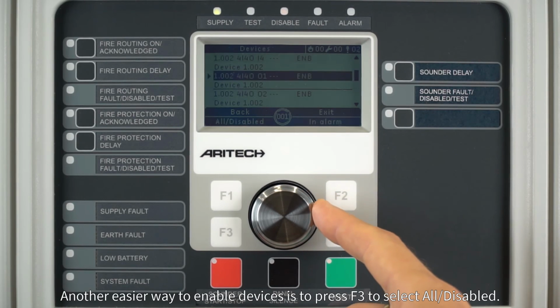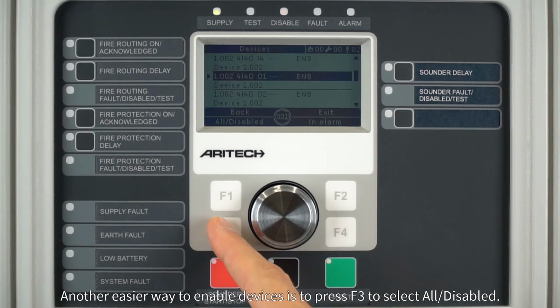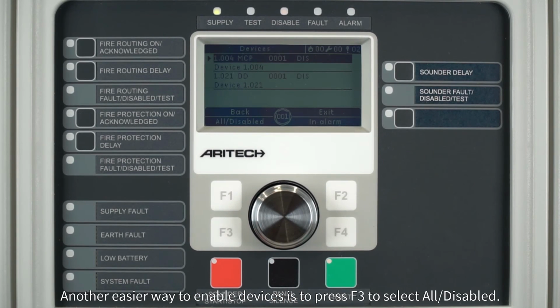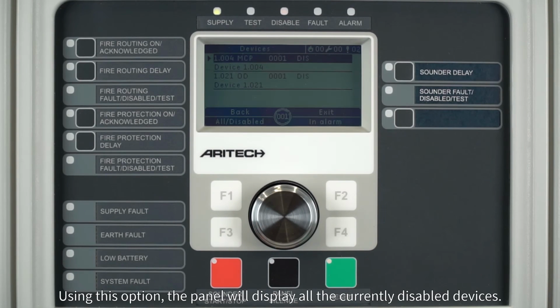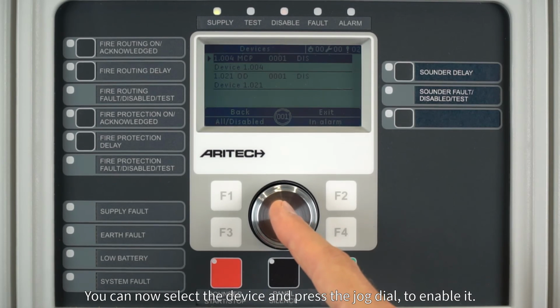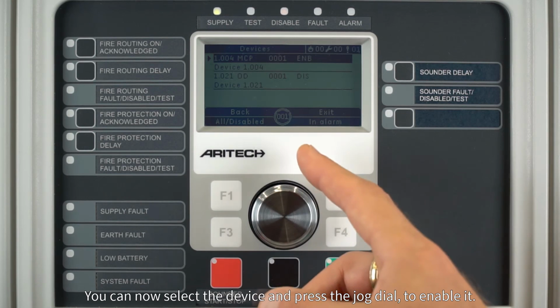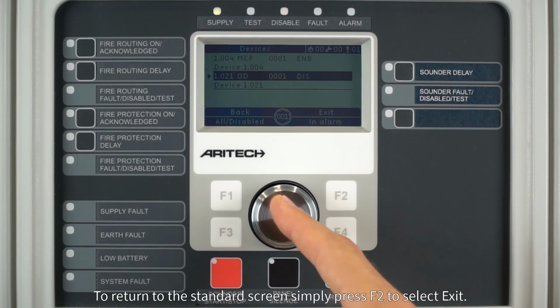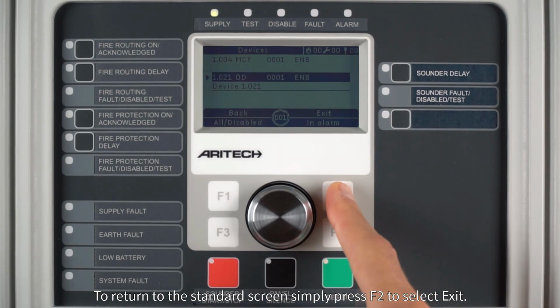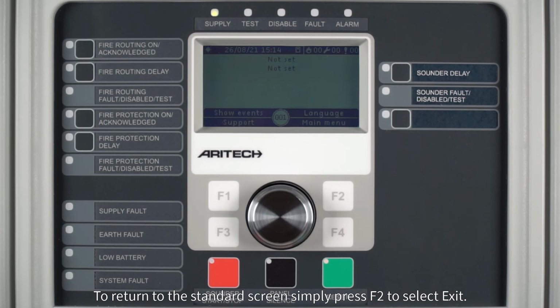Another easier way to enable devices is to press F3 to select all disabled. Using this option, the panel will display all the currently disabled devices. You can now select the device and press the jog dial to enable it. To return to the standard screen, simply press F2 to select Exit.